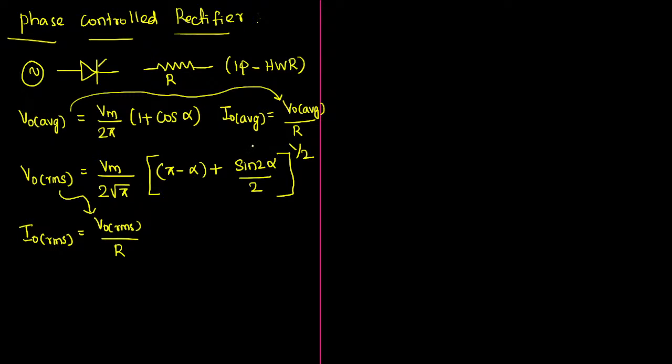Fine. Next, how do I explore the input power factor, IPF? We know the formula. We have to identify the total power consumed by the load on the output side. But here we are considering only RMS parameters. Don't forget that. As usual, the input kVA rating will be the apparent power, so for apparent power also we must consider RMS parameters.